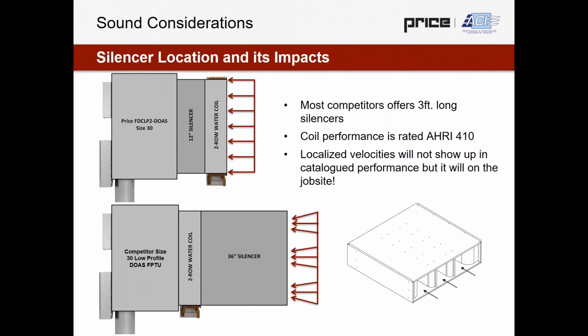The other key consideration is where we choose to mount our silencer. We have both a 1 foot and a 3 foot silencer option. And as I stated, we mount this in between the water coil and the piece of equipment. This is really critical because of the way that coils are tested on these pieces of equipment. So our coils are tested as per AHRI 410. And AHRI 410 essentially takes that coil and treats it as its own certified separate accessory.